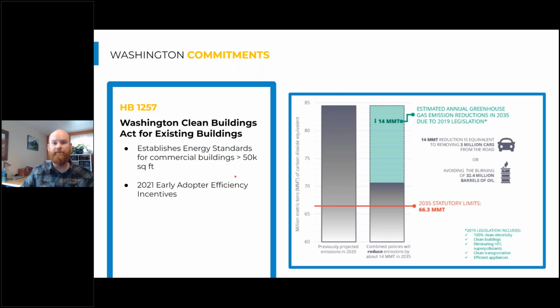One of my coworkers at Ecotope recently finished, about a year ago, an energy audit for this House bill to really look at where the energy was being used in that building. And with simple control changes and adjustments, they were able to save about 25% of the annual energy use. So a quarter reduction in annual energy use for one building based only on control changes and control optimizations.